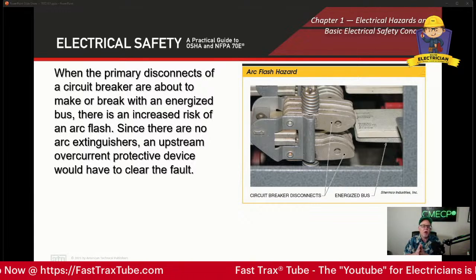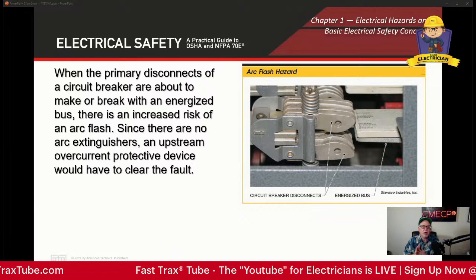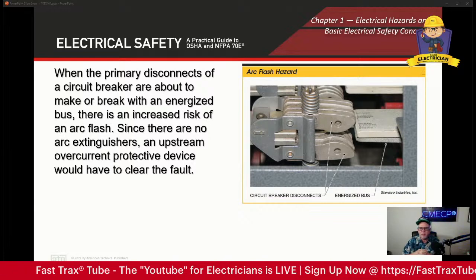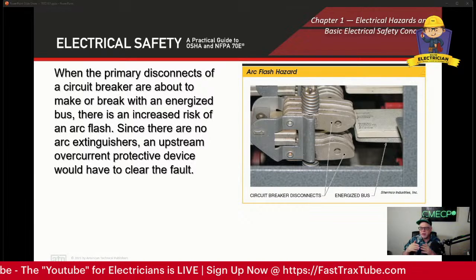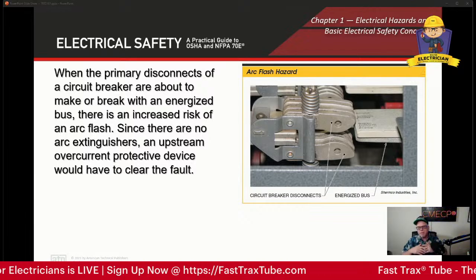Since there's no arc extinguisher, an upstream overcurrent protected device would have to clear the fault. So we have an arc, something takes place, and upstream protection clears the arc.